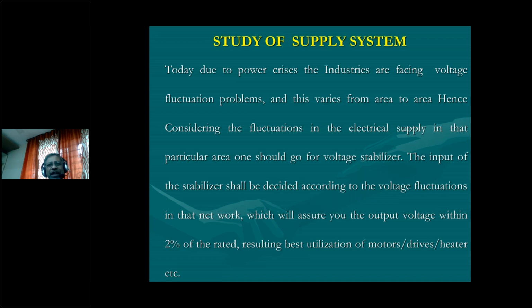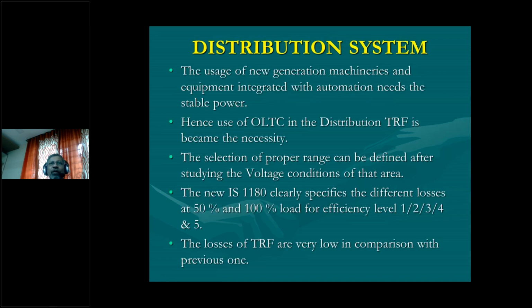So for particular such types of application, such as medical instruments or costly CNC machines, instead of a conventional stabilizer you can go for a solid state stabilizer, what we call a digital stabilizer, whose correction time is hardly 20 milliseconds, which is very sensitive. So the selection of equipment is also very important in my opinion. Let us move to the next slide. Now let us come to the distribution system. Actually, this slide got interchanged.